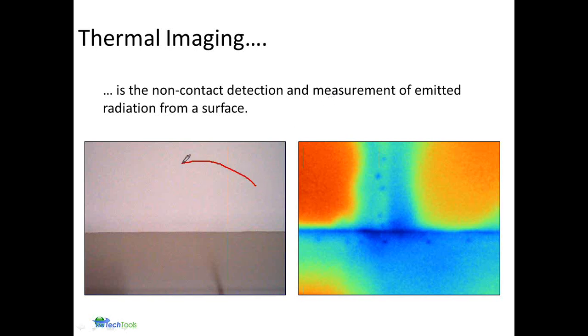What we see on the left-hand side is the ceiling and wall where they join. The image on the right, thermally, shows us the nails and screws holding the sheetrock onto the wall, and we're seeing some anomaly at the joint area. This area is a roof support beam going across the ceiling, just giving us an idea that there are some thermal issues going on, or some thermal differences behind the surface.